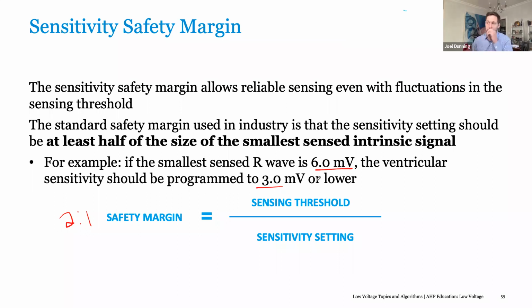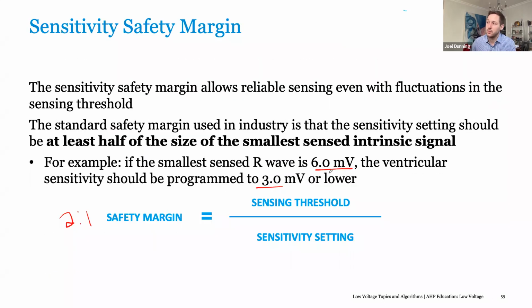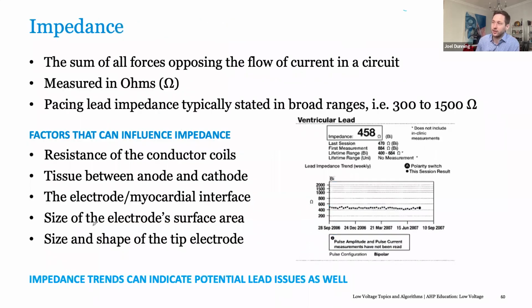And if you just set it for 5 millivolts, for example, we may be under sensing when the patient is lying prone, which means we could be pacing either into vulnerable periods or pacing when the patient doesn't need to pace, which is obviously not ideal. So just things to keep in mind. Everything in pacing in general is a 2-to-1 a lot of times. 2-to-1 capture margin, 2-to-1 safety margin. When we talk about implants with leadless, 2-to-1 plays a major factor as well.